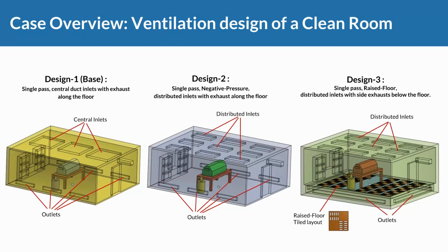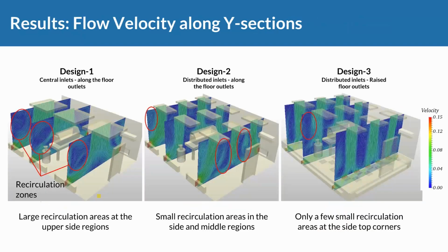If I remember correctly, I'm pretty sure this simulation was set up using the same mass flow at the top. So we would not need more energy to power any of these systems. It's the same energy, and the question is how effective these different HVAC layouts are with respect to contaminant control. Contaminant source, we talked about it, same story. You drop these models into SimScale, set up the physics, run the analysis, and then you can do such comparative studies.